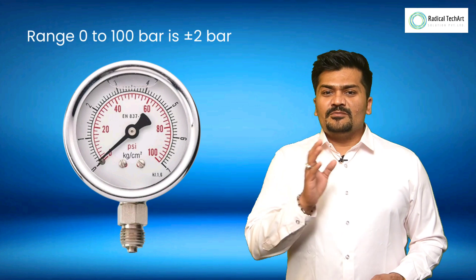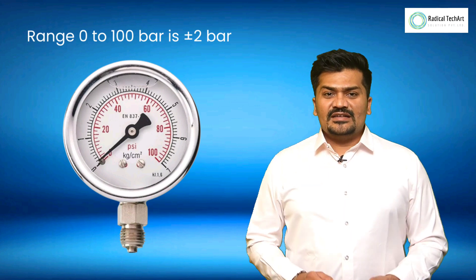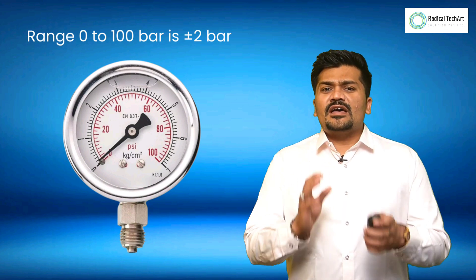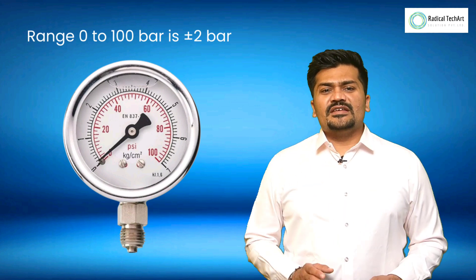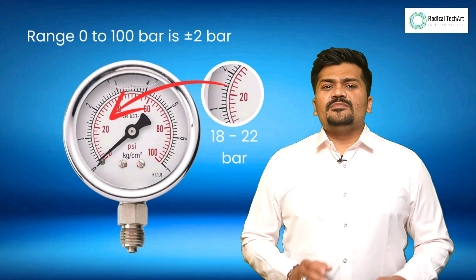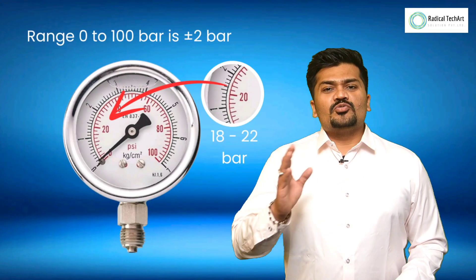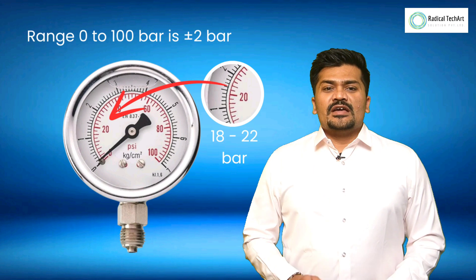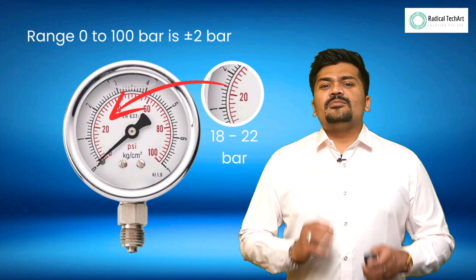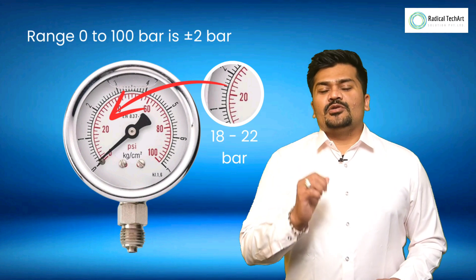For example, if we are measuring a reading of 20 bar, then the actual value can be anywhere between 18 bar and 22 bar. Any reading within that range is considered an accurate reading.